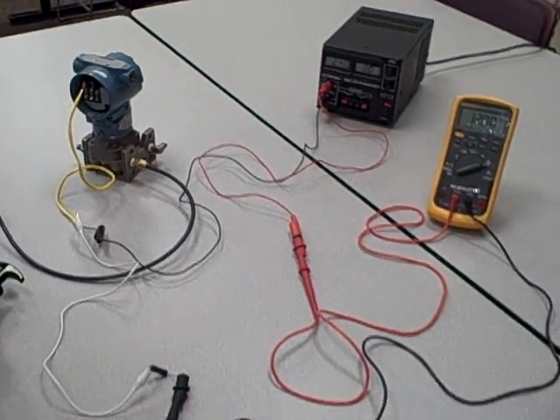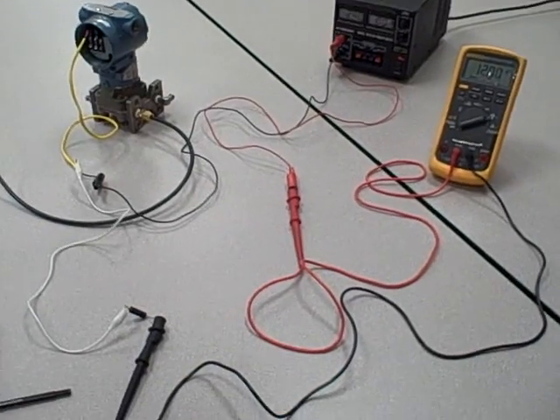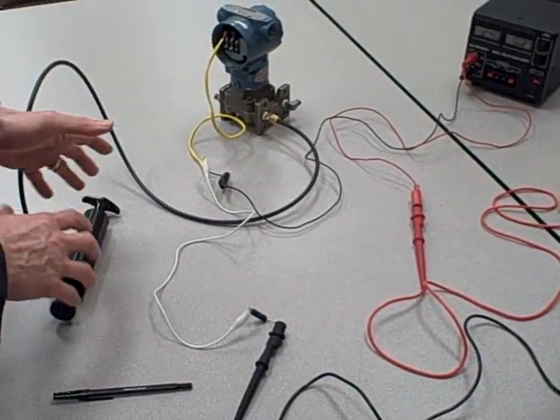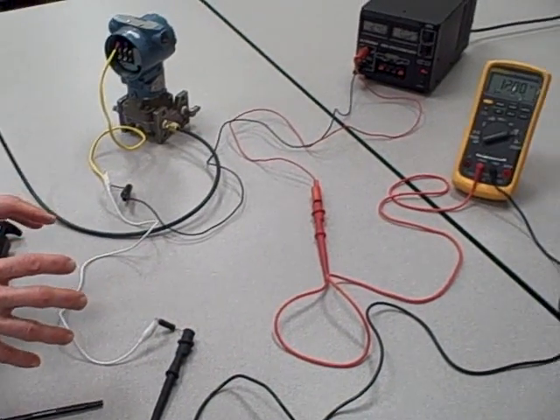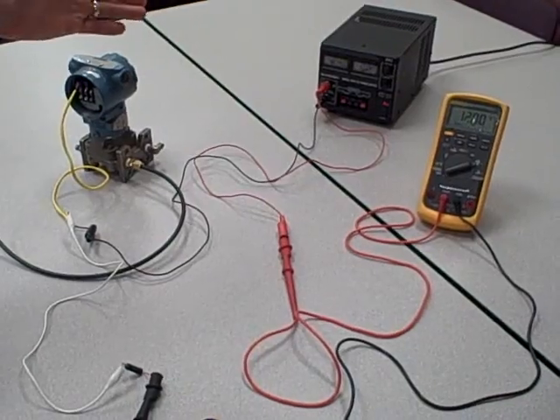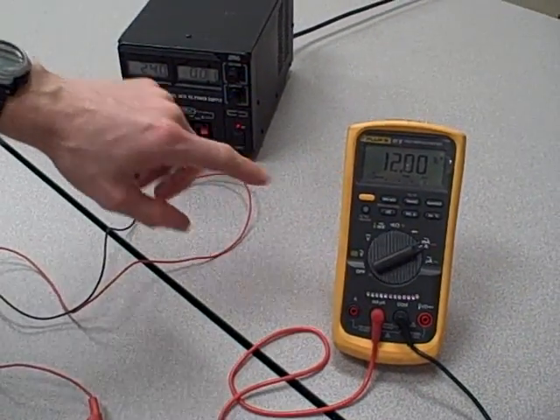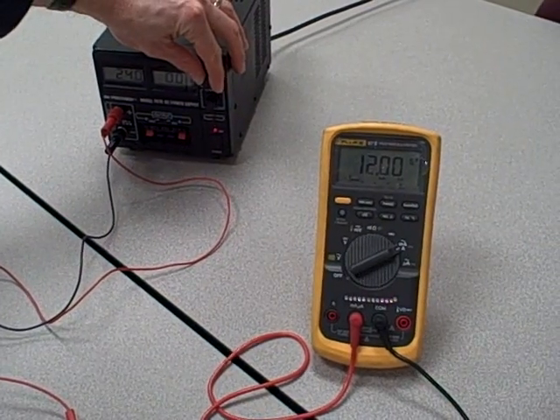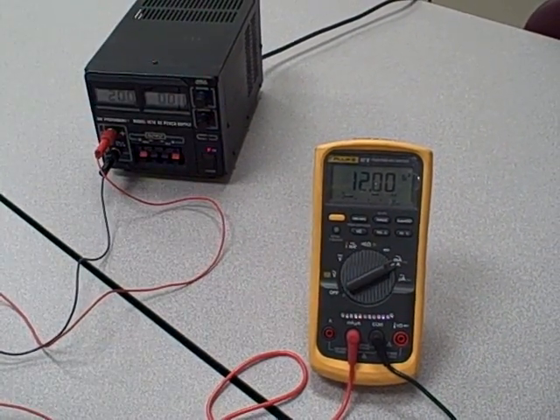What I'd like to demonstrate to you is how this current, this 12 milliamp current that we see, is dependent only on the amount of pressure we apply to the transmitter and is not dependent on other factors like loop resistance or power supply voltage. For instance, watch what happens when I begin to change the voltage here. It's now 24 volts, we have 12 milliamps. Watch as I decrease the voltage from 24 down to about 20. Notice the current doesn't change at all.